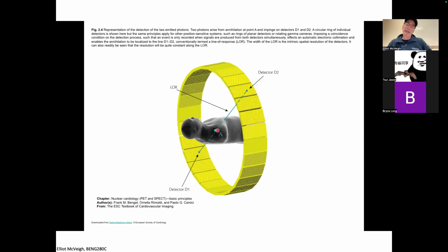And I say, well, my positron was emitted somewhere along this very thin straight line, right? So it's highly localized. It's not localized in this dimension, obviously, but it's highly localized in the axial dimension around that line. And we use these as lines in projections to then create a 3D image, right? What else is there to know about that?